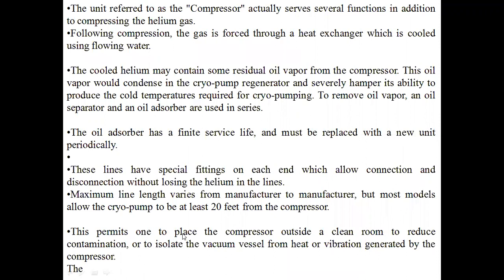This permits one to place the compressor outside a clean room to reduce contamination, or to isolate the vacuum vessel from heat or vibration generated by the compressor. That's it.